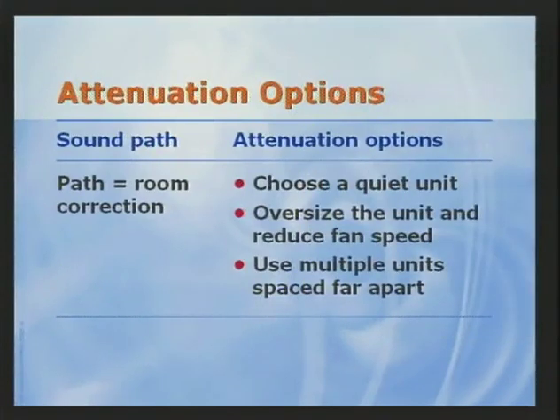The obvious way to meet a sound target using an in-room system is to choose a sufficiently quiet unit. Other things to consider are choosing an oversized unit and reducing the fan speed, or using multiple units provided that they can be located far enough apart not to add acoustically. Finding in-room equipment that meets the 35 dBA requirement may be difficult, but as the demand for these units increases, it is likely that quieter units will become available. And it really becomes important to analyze those in-room units in an acoustic analysis to find out whether or not the sound power levels are low enough for us to apply in that particular space.